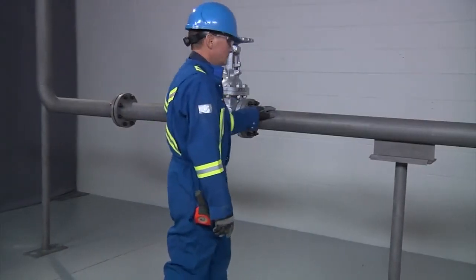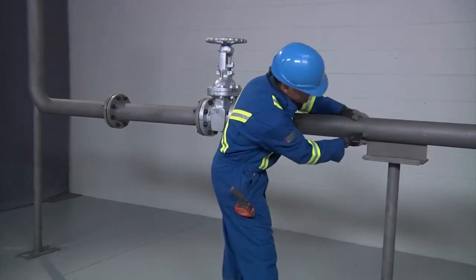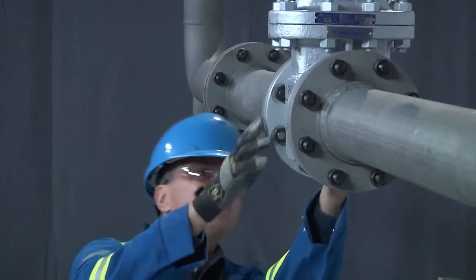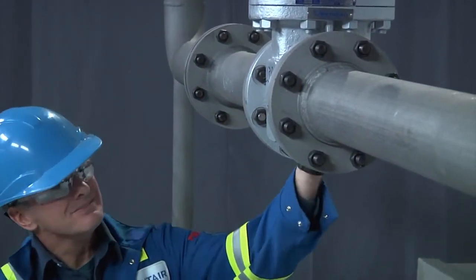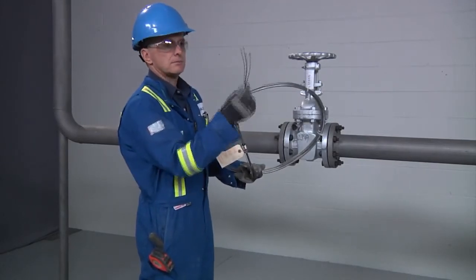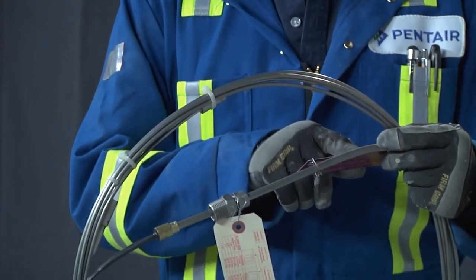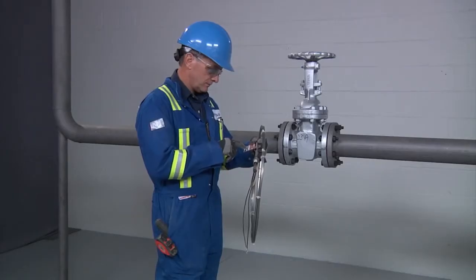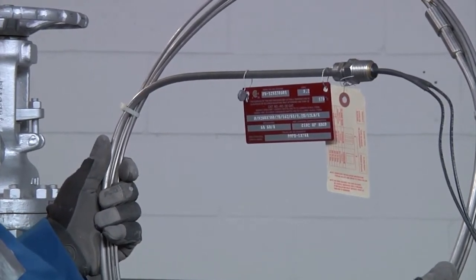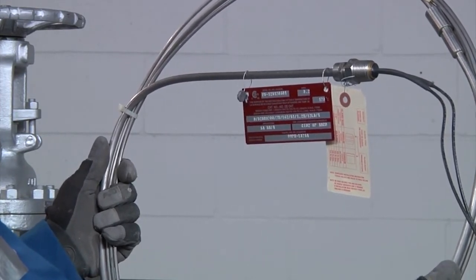4. Inspect the piping for any burrs, rough surfaces, or sharp edges and remove them if necessary. 5. Verify that any surface coatings are dry to the touch. 6. Inspect the cable coil for any nicks and cuts. 7. Ensure that you have the correct heating cable. MI heating units are individually designed for each section of pipe and it is critical that you ensure the correct heating unit is installed on the specific section of pipe that it was designed for.